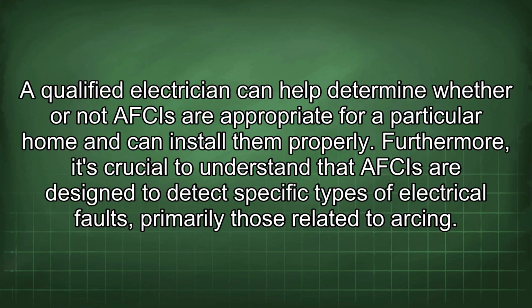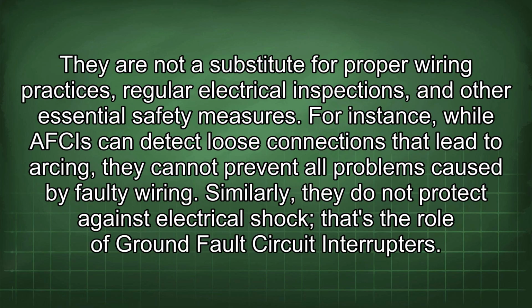Furthermore, it's crucial to understand that AFCIs are designed to detect specific types of electrical faults, primarily those related to arcing. They are not a substitute for proper wiring practices, regular electrical inspections, and other essential safety measures. For instance, while AFCIs can detect loose connections that lead to arcing, they cannot prevent all problems caused by faulty wiring. Similarly, they do not protect against electrical shock. That's the role of ground fault circuit interrupters.